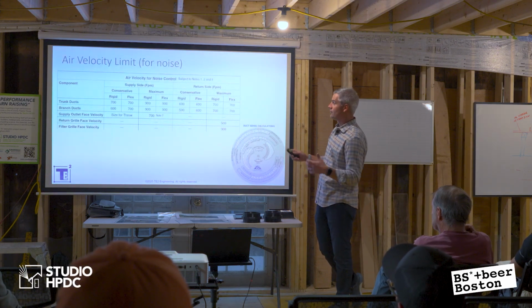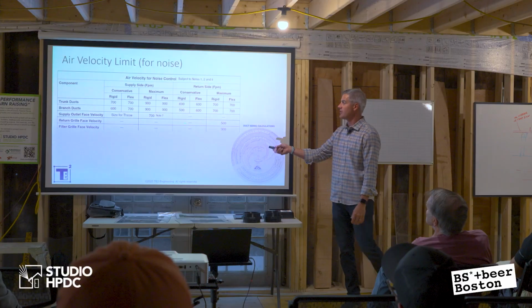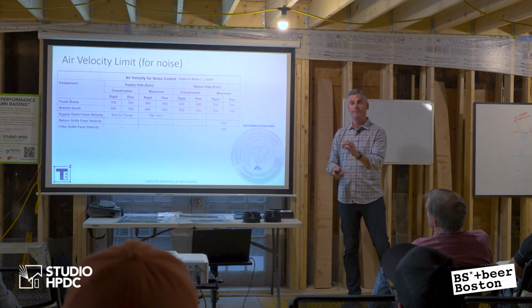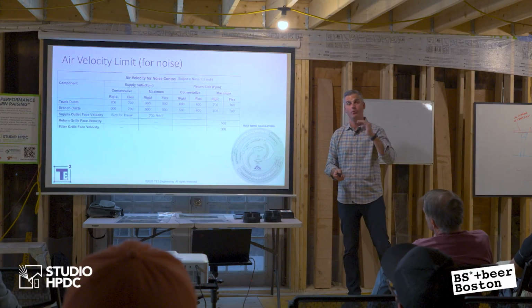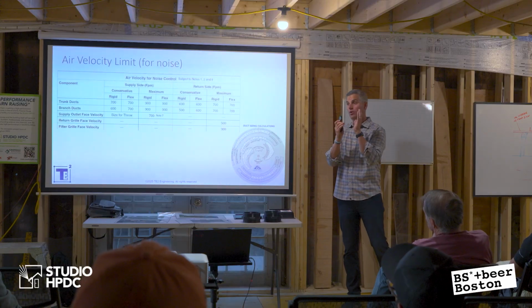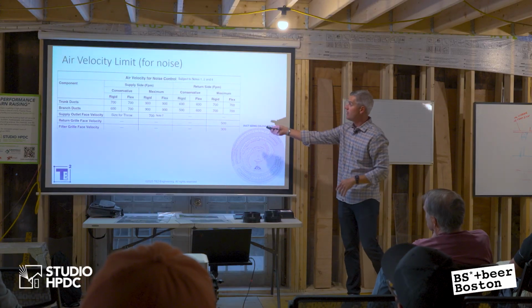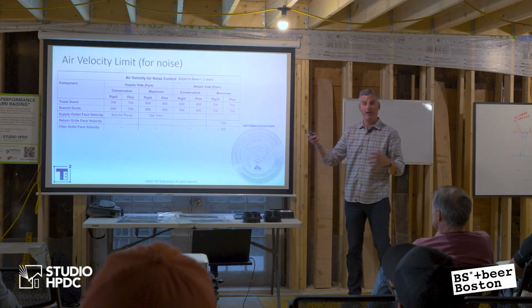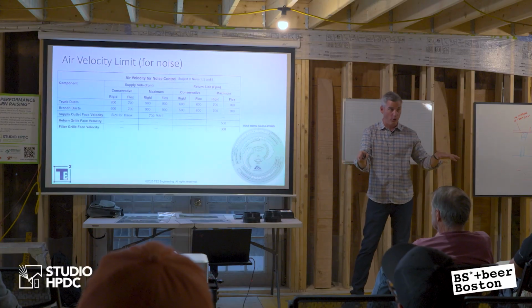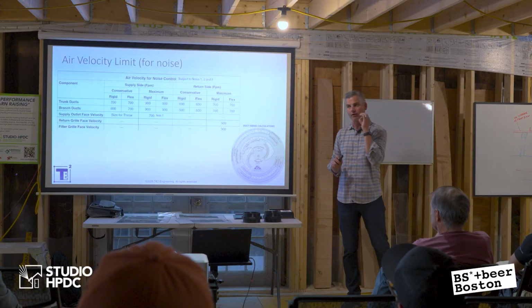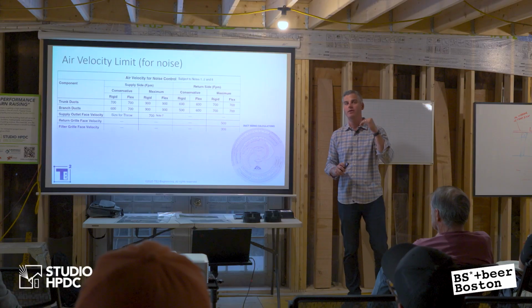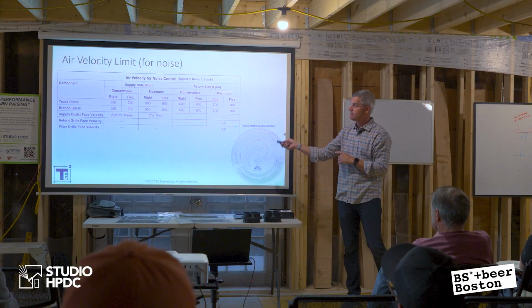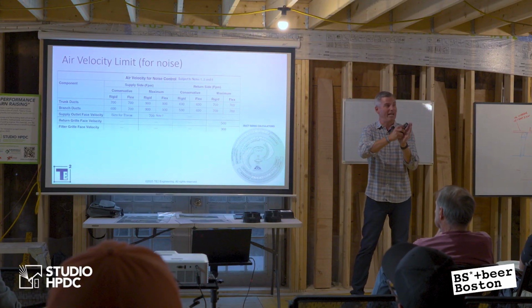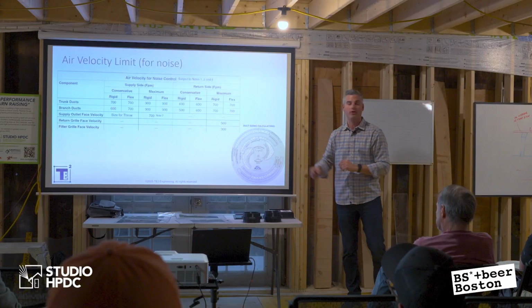And the last one is just air velocity limits, just making sure the velocity in the ductwork is quiet, right? And that's where velocity comes in. If I move the air too fast through the register, or too fast through the ductwork, exceeding these velocities, I'm going to have noise issues. It has nothing to do with performance, just noise. If I hear that rattle, that vibration, that humming, that's all because of this, right? So that's another aspect you have to review before you send those drawings out.